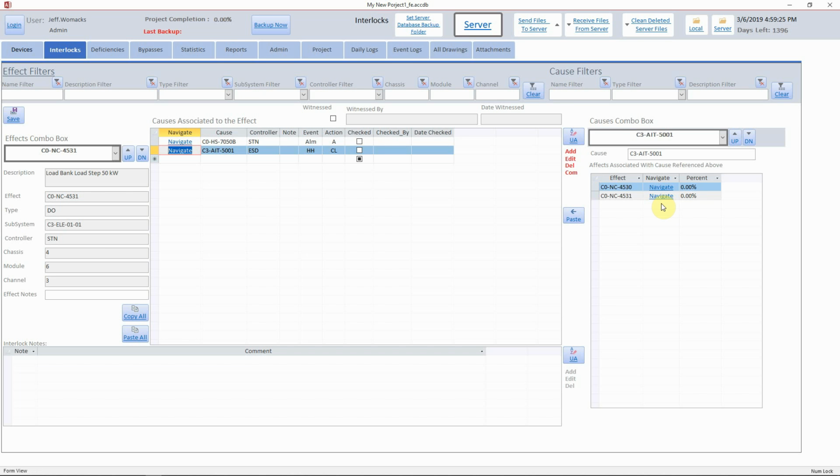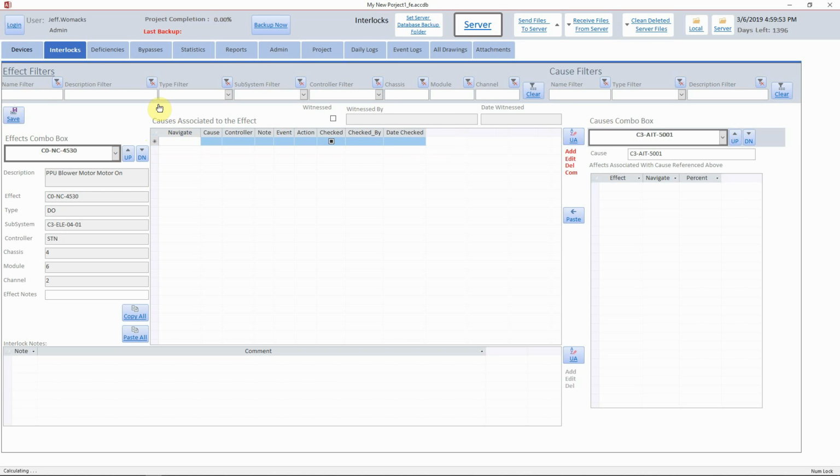That way I can cross-reference and basically audit the cause and effect matrix to make sure it makes sense and raise any questions as I'm going. So in the event that you're fully confident in the cause and effect matrix, and you know that the export from it is 100%, what you can do is import your full cause and effect matrix from an Excel spreadsheet.